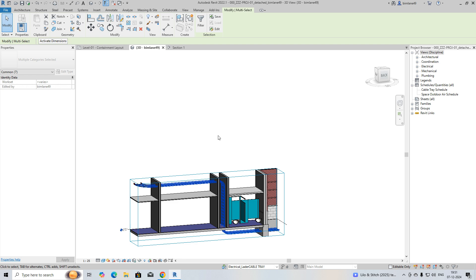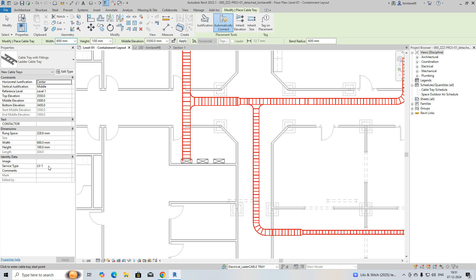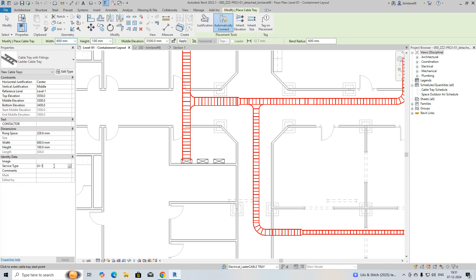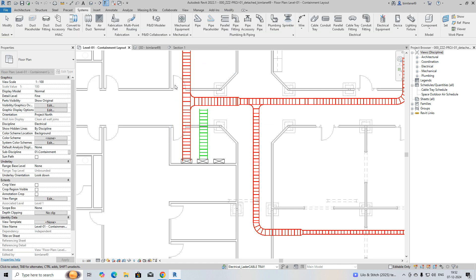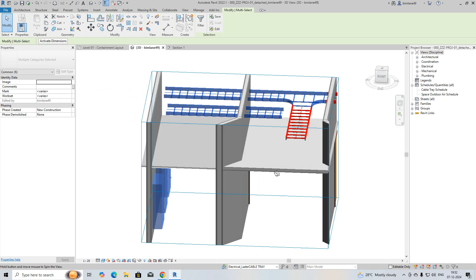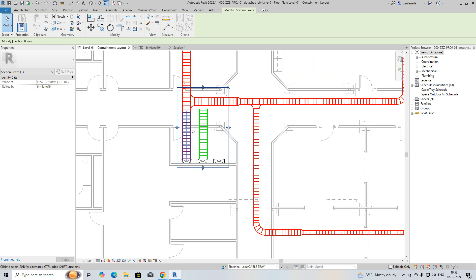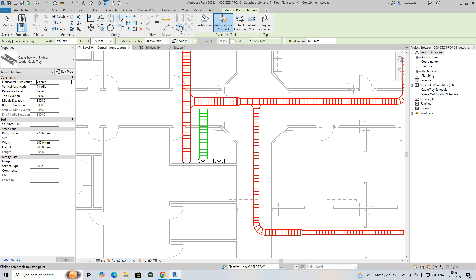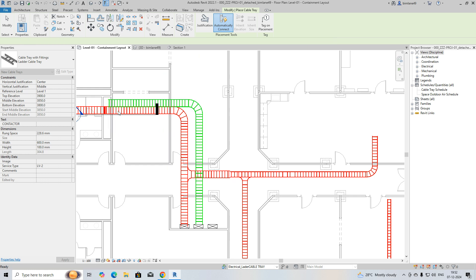You can see all the cable trays running through here. Now I'll make another cable ladder, but this time I'm changing the service type. Go to System, Cable Tray, and change to Service Type 2. Make it a 600mm cable tray going this way. If it goes up to here at the same level as the other cable ladder, there could be a clash. So we need to change the elevation — use 'Create Similar' and change the elevation to 3850, then draw the cable ladder from there.